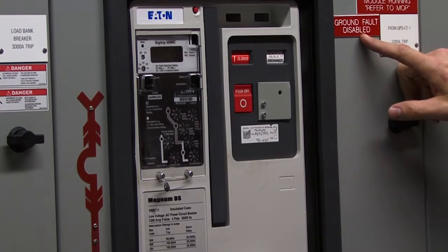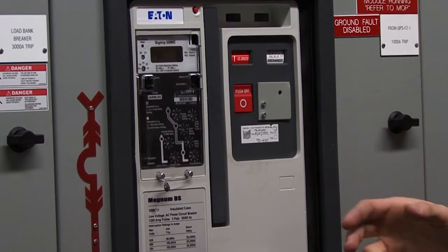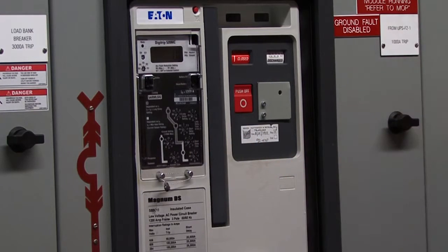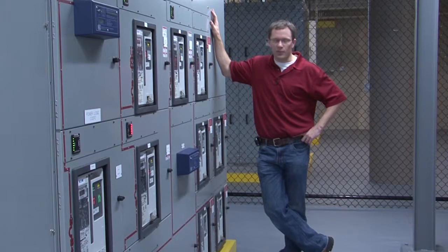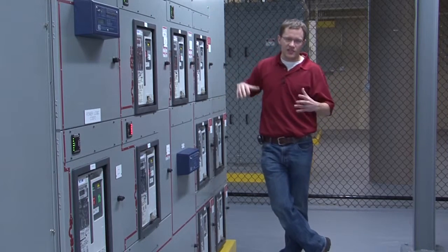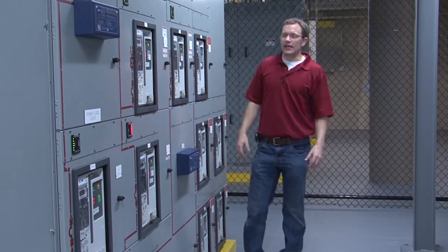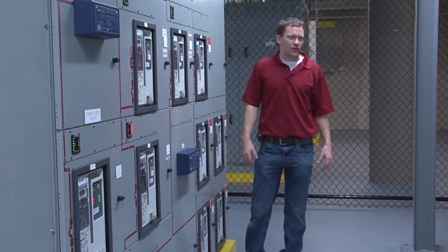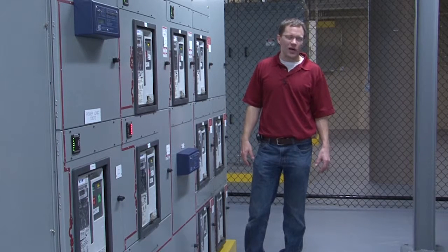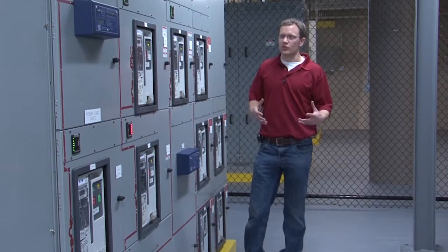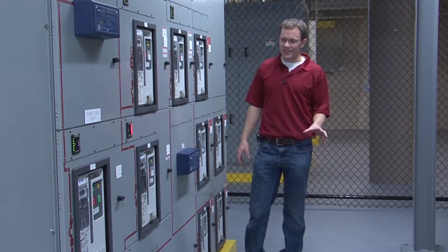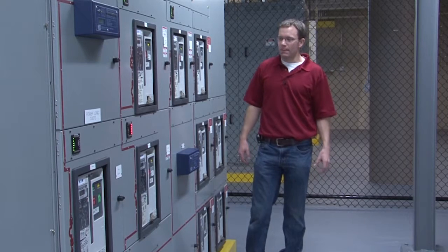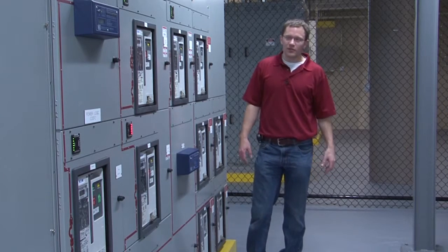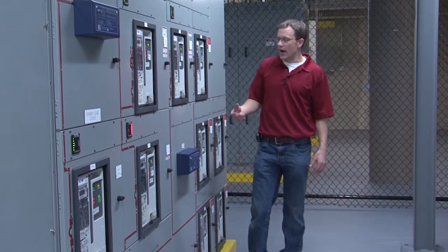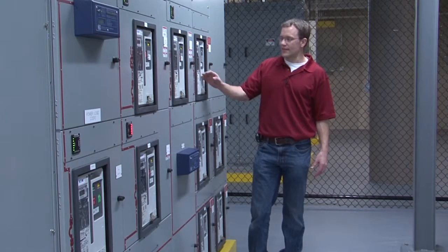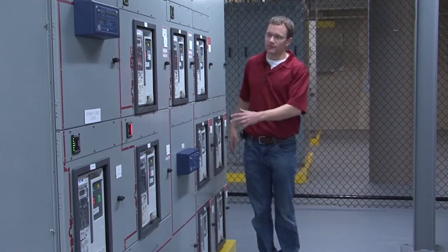In addition, ground fault is disabled. When they ordered these breakers, they ordered them with ground fault protection. But the way that this system is relative to their existing, it doesn't lend itself to ground fault protection that won't cause nuisance trips. So it's very difficult to be able to place the neutral CTs in a location that would properly sense a ground fault and not trip when it shouldn't. So the decision was made by the engineer of record to disable ground fault protection at this point.